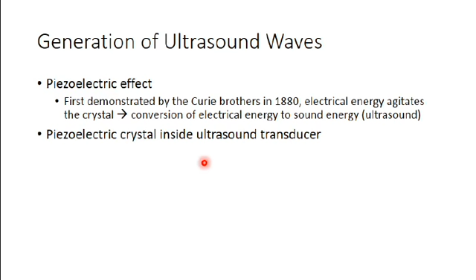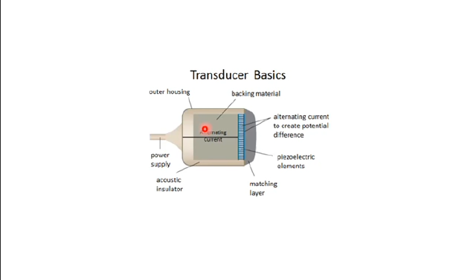Now, the ultrasound transducer has a number of piezoelectric crystals packed inside. So this is how an ultrasound transducer will look if you cut it open. These blue things here are actually many crystals, all packed tightly side to side. What happens is the power cable that runs along the cord of the ultrasound transducer produces an electric current that goes and hits these piezoelectric elements of the crystal. Now these crystals will start vibrating, and when they vibrate, they produce sound energy that comes from the head of the crystal.